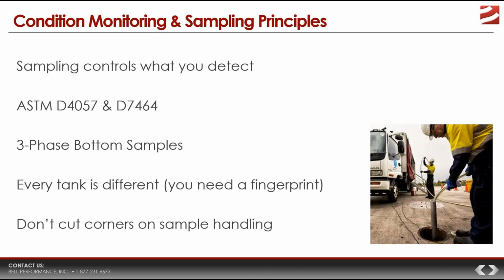So in addition to doing things like making sure that your fuel samplers and equipment are sterile and using unused fuel sample containers to put your samples in, you want to take your pulled samples, get them on ice and then into the refrigerator if there's going to be any significant amount of time between when you draw the sample and when you can test them for microbes. So that's a very basic summary of the important practices in condition monitoring.